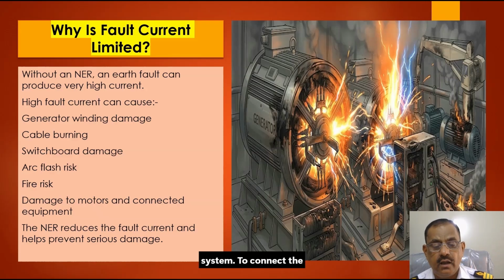To summarize, the neutral earthing resistor connects the generator neutral to the ship's hull through resistance. During an earth fault, it limits fault current and helps protection relays detect the fault. A properly maintained NER improves safety and protects the generator, cables, switchboards and shipboard electrical system.